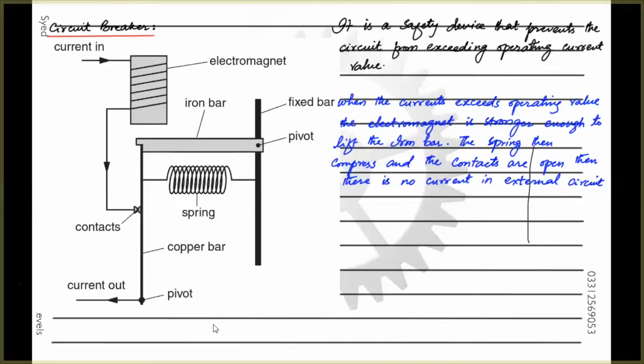Why should it not be replaced? Sir, because it has an electromagnet and a reset button. When the current is again normal and less than the operating current value, you can reset the iron bar back to its position. The spring will again be stretched and current will flow through the external circuit. So whenever the current gets normal, you press the reset button, the iron bar comes back to the same point, and the appliance starts working again, right?